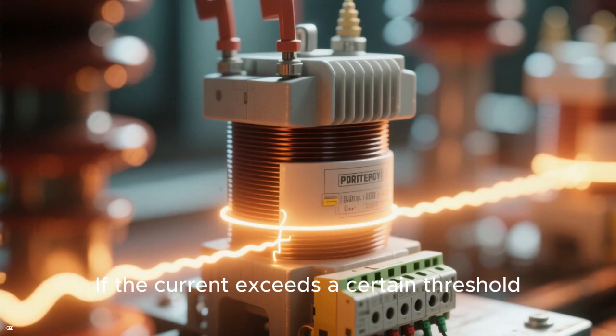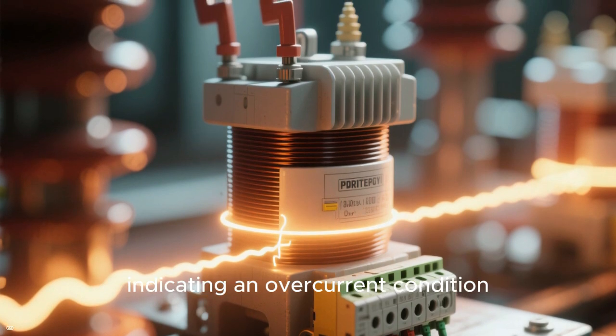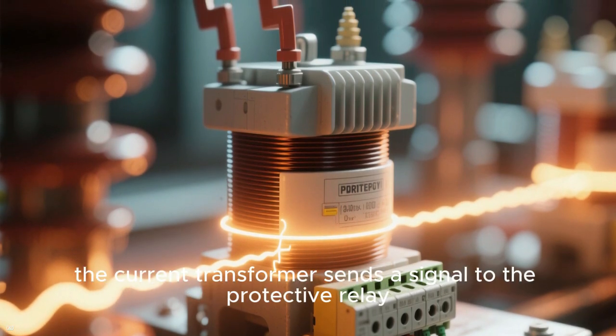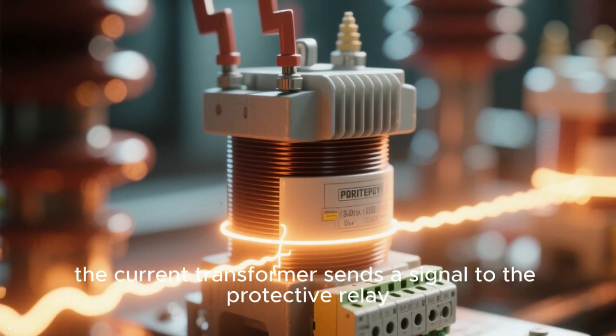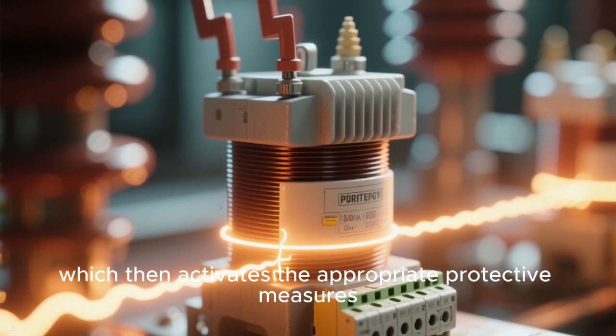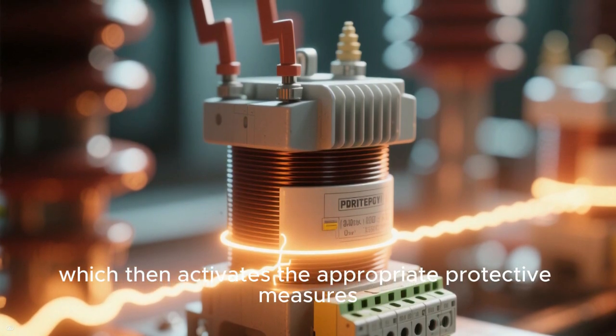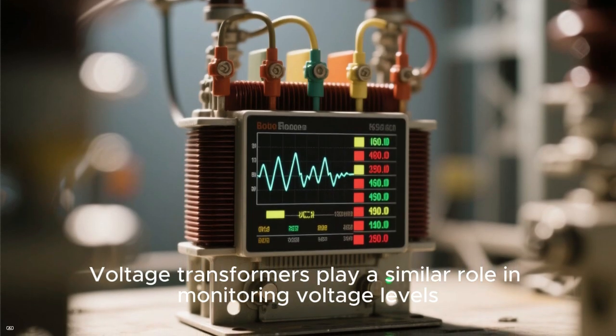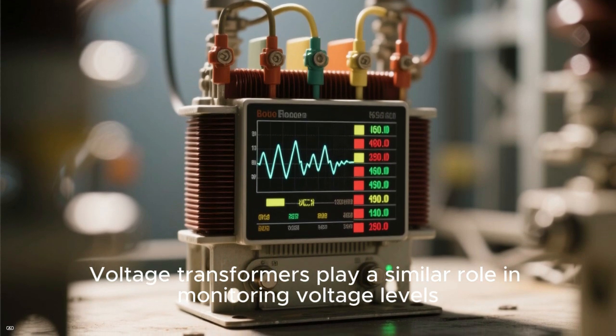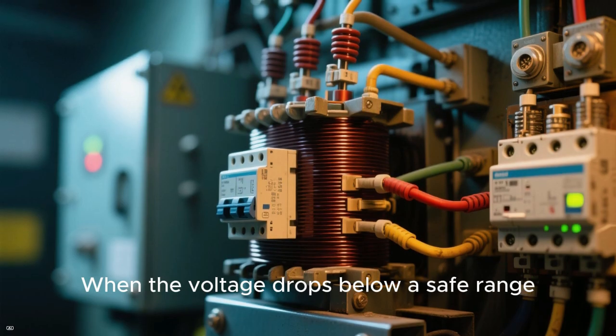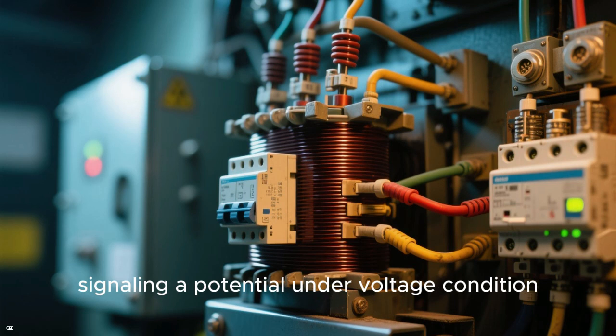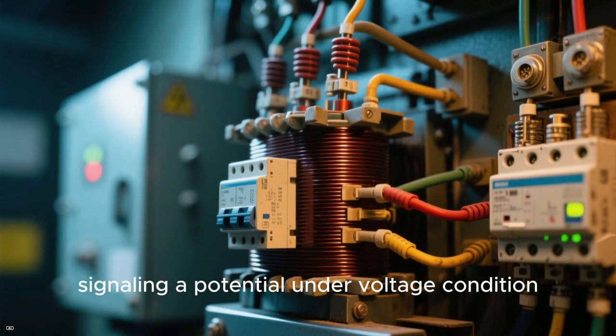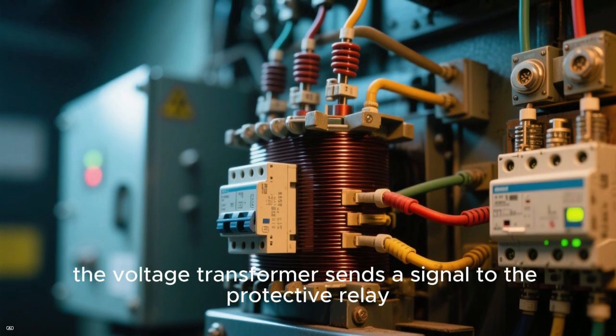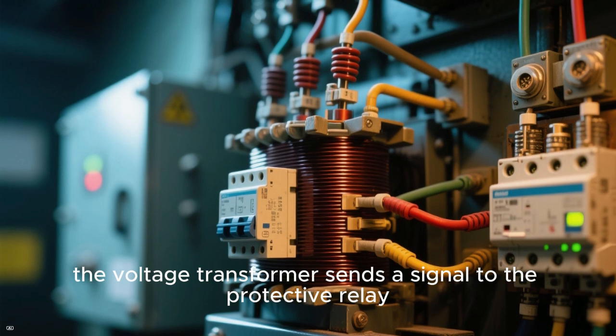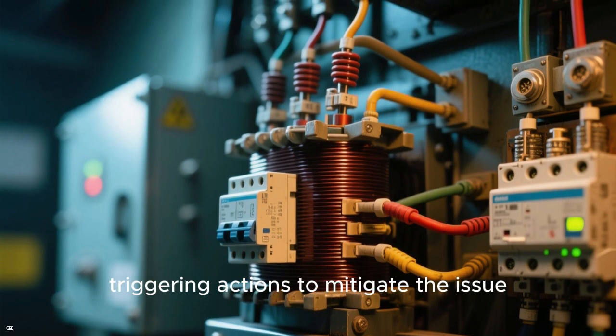If the current exceeds a certain threshold, indicating an overcurrent condition, the current transformer sends a signal to the protective relay, which then activates the appropriate protective measures. Voltage transformers play a similar role in monitoring voltage levels. When the voltage drops below a safe range, signaling a potential undervoltage condition, the voltage transformer sends a signal to the protective relay, triggering actions to mitigate the issue.